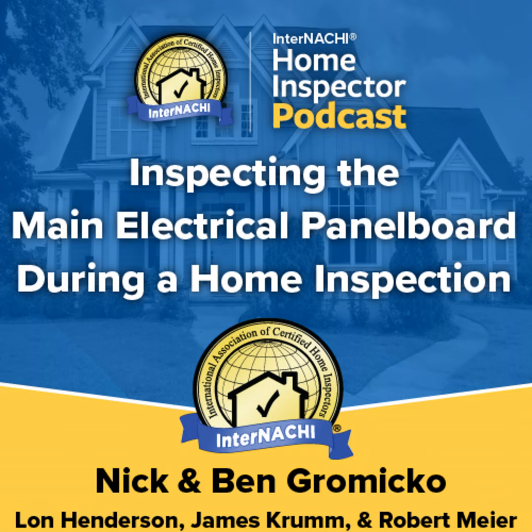Let's begin with InterNACHI's Home Inspection Standards of Practice. According to the InterNACHI Home Inspection Standards of Practice, found at nachi.org/SOP, the inspector is required to inspect the service entrance conductors, the main service disconnect, panel boards, overcurrent protective devices, including circuit breakers and fuses, and service grounding and bonding. The home inspector is not required to remove panel board cabinet covers or dead fronts.